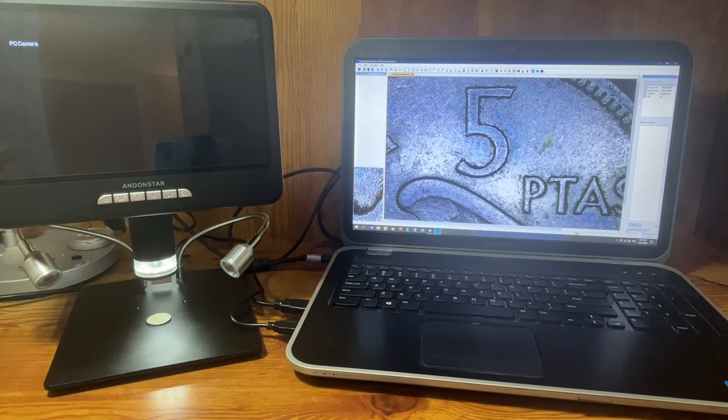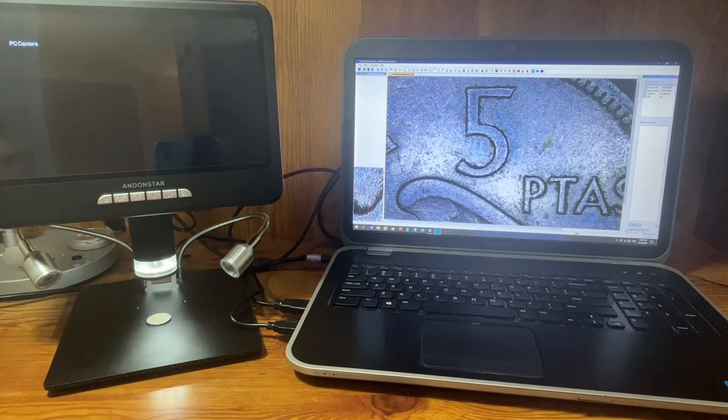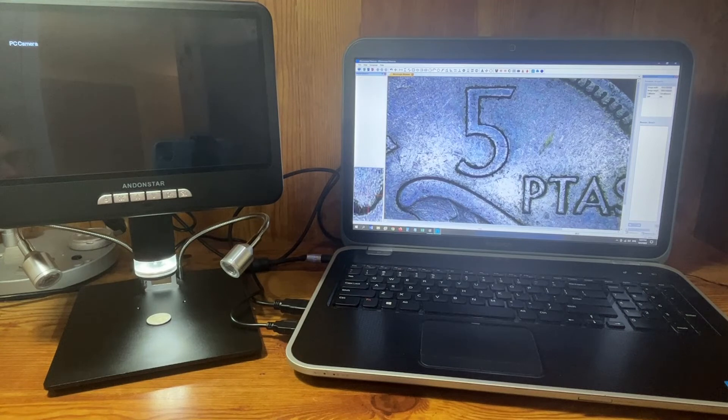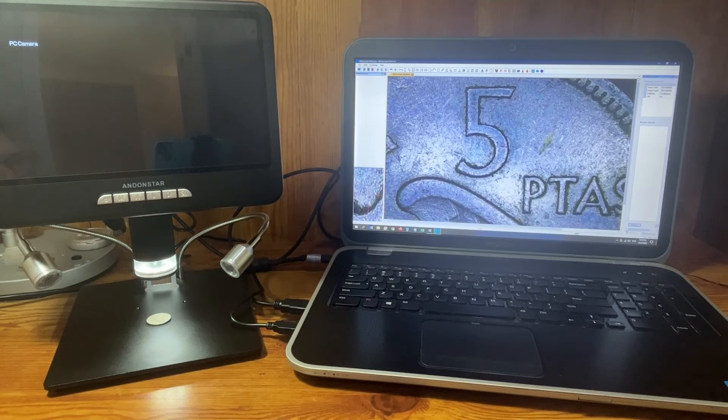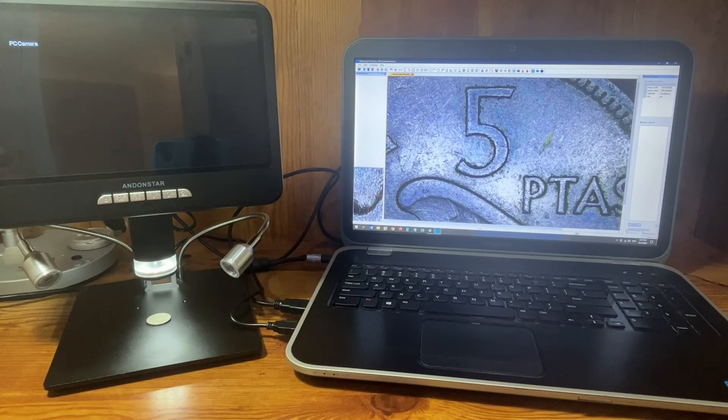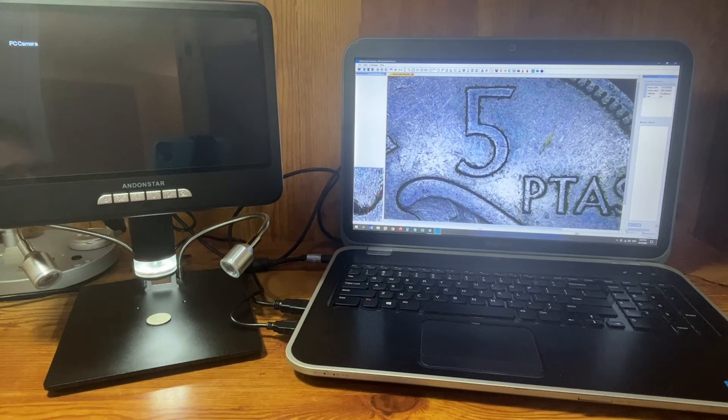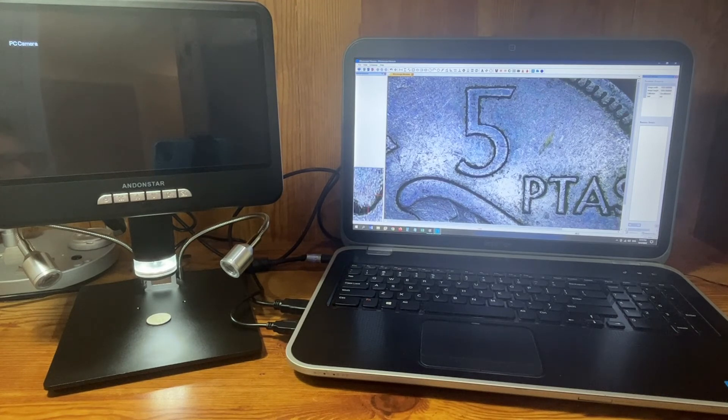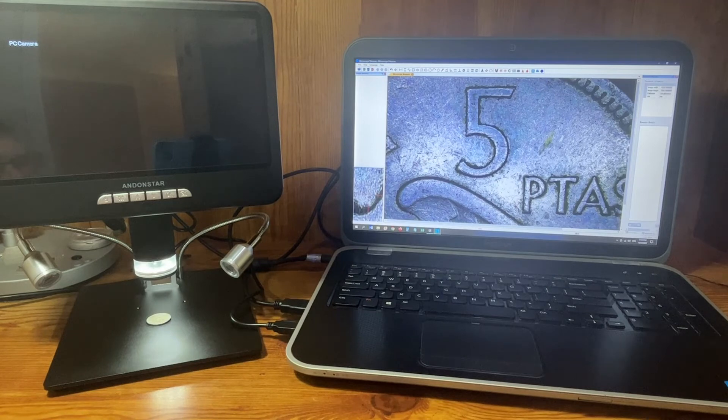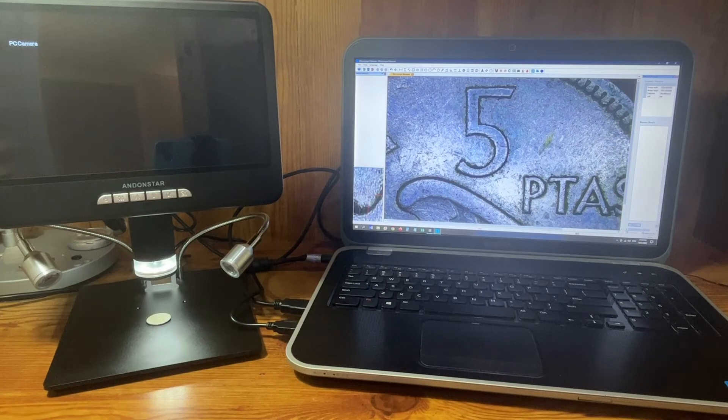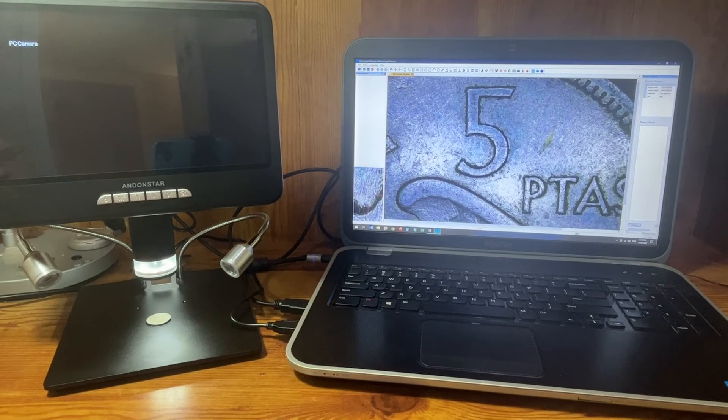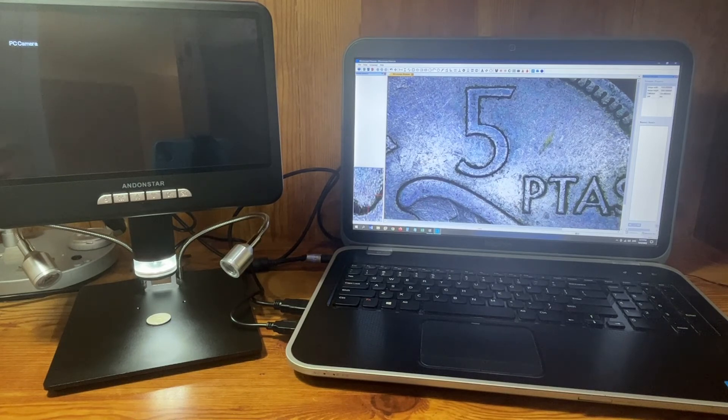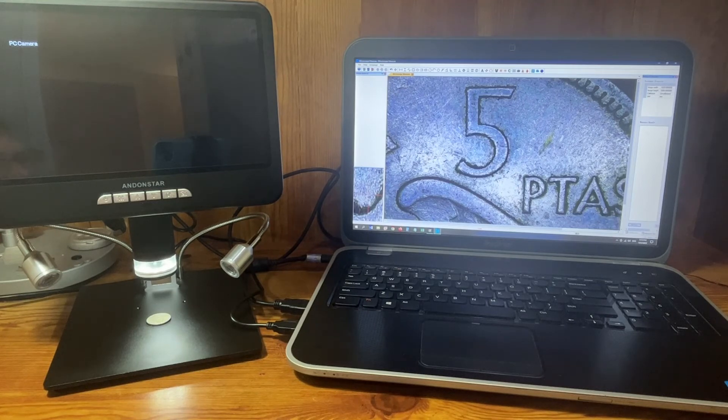Now of course if you want to do any of those measurements, you have to be able to calibrate a length to start with. So I still had to do the same thing back when I was in college. If I wanted to measure the length between two points, I first had to tell the software the length. You know, and you could do that pretty easily if you took like a ruler that is a fairly good ruler and put it under the microscope here that's the same distance away from the microscope lens as the surface of your coin, and then take a picture of that, measure between two points, and then you tell the software that that distance is two centimeters or whatever it is. And then it's calibrated to know when once you measure how long something is.